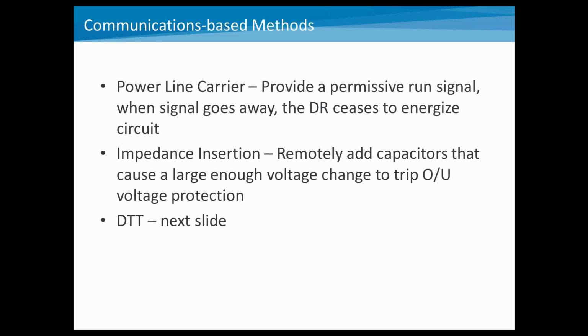So as we move on to communication-based methods of anti-islanding, there's a variety that we'll talk about quickly. First, power line carrier. Typically this is employed where you use a permissive run signal at all times on the grid. And then when the signal goes away, the DR recognizes that and ceases to energize the circuit. There's things like impedance insertion, where you may have a capacitor bank located near your DR that's remotely controlled, and if you go into an island condition, then you can add those capacitors and cause the over-under voltage protection to activate. And then one that's also used quite a bit, especially for larger scale systems, is what's called direct transfer trip, and we'll talk about that on the next slide.